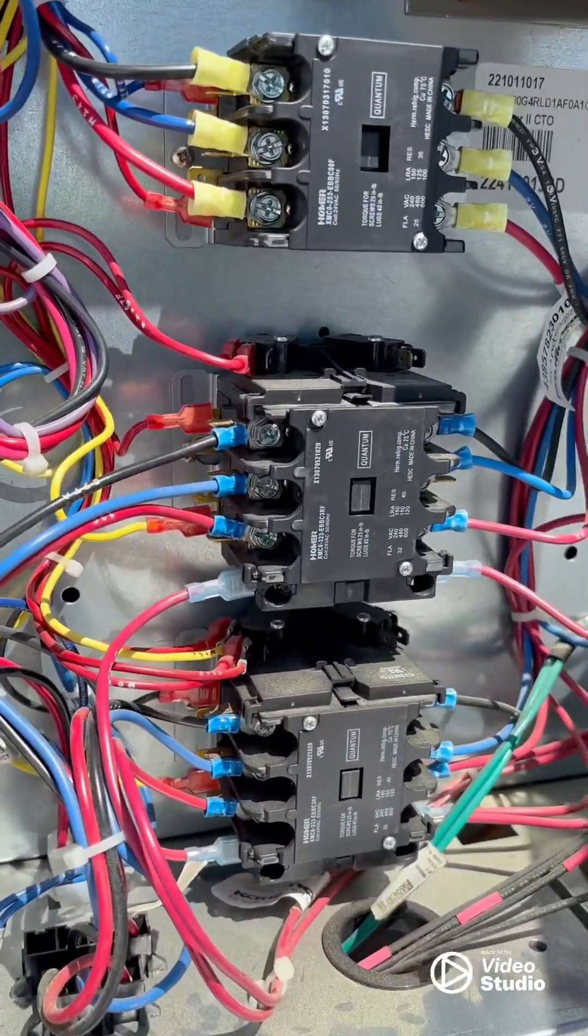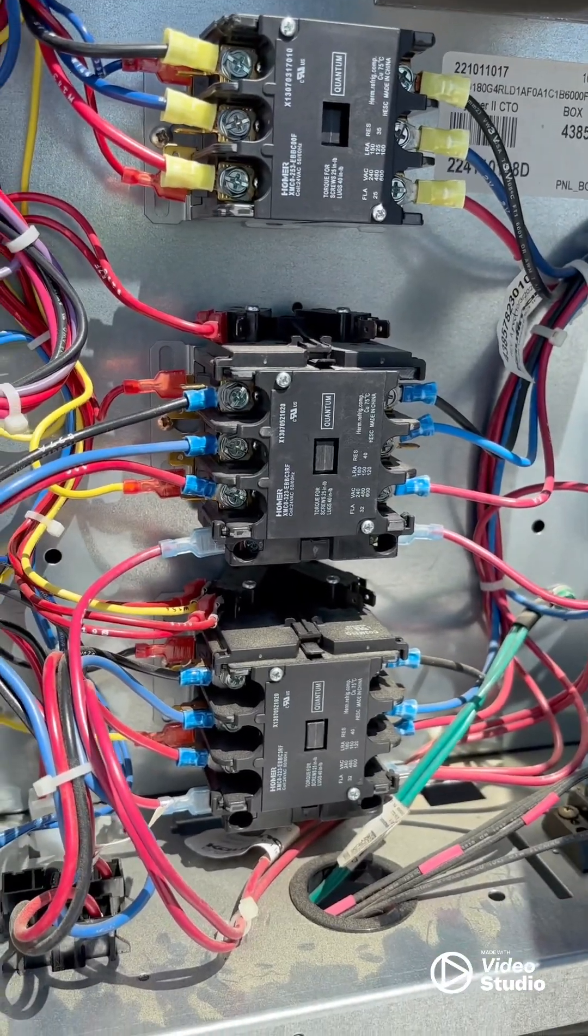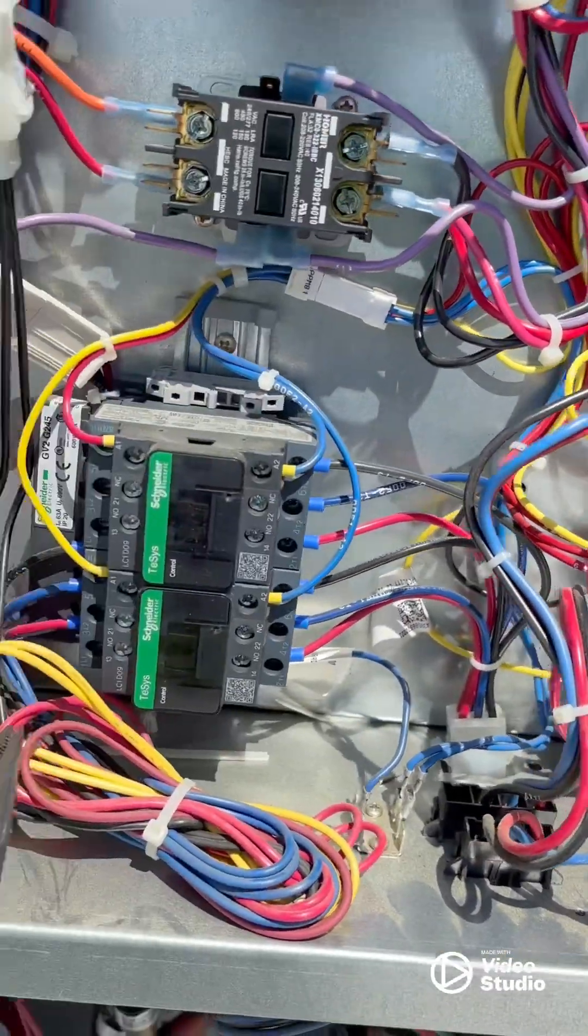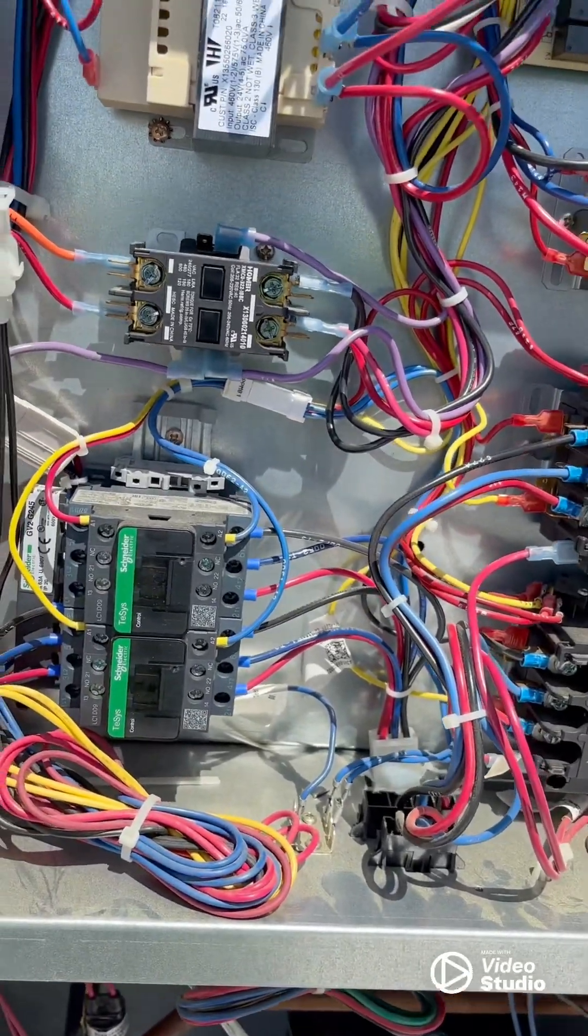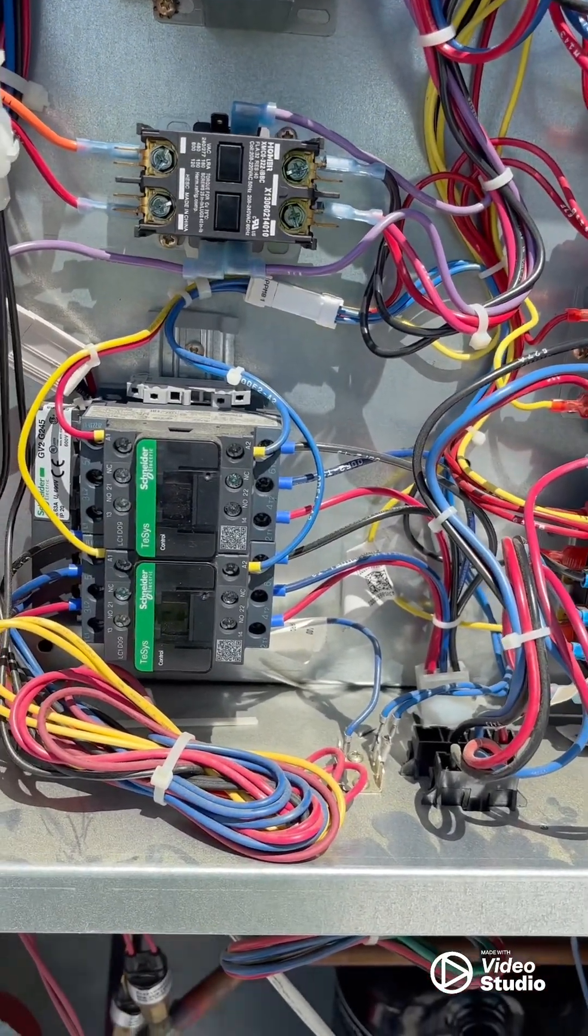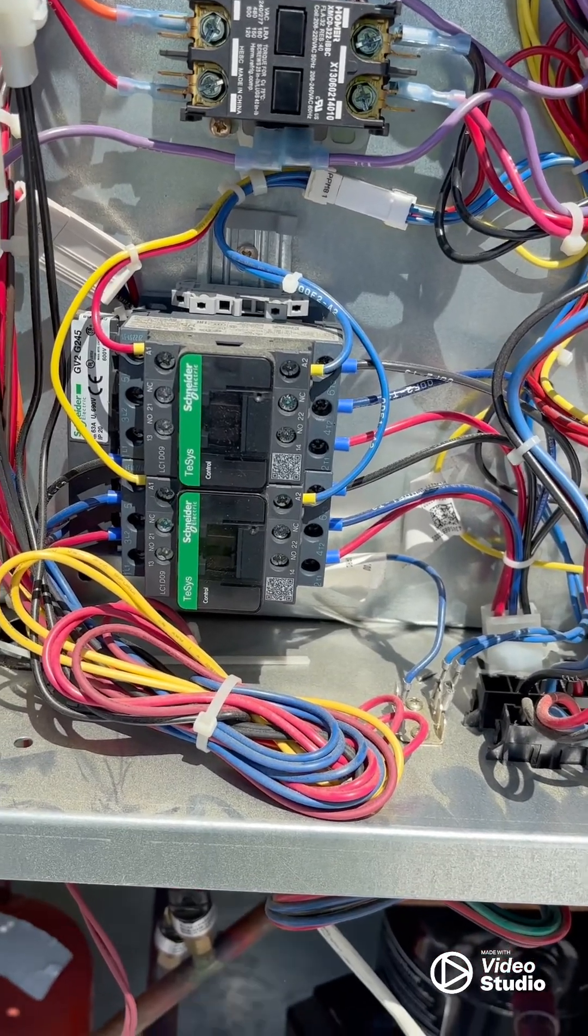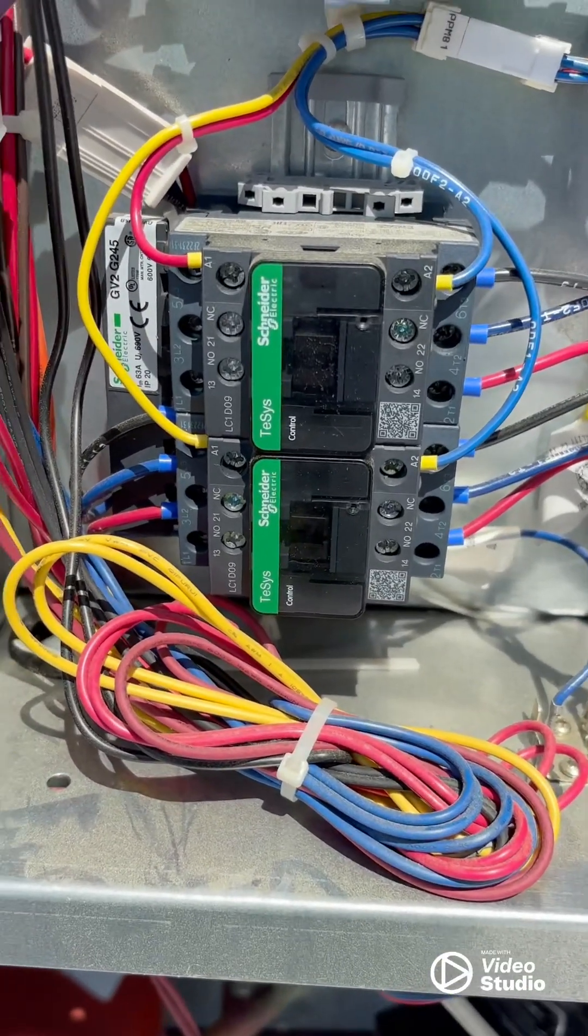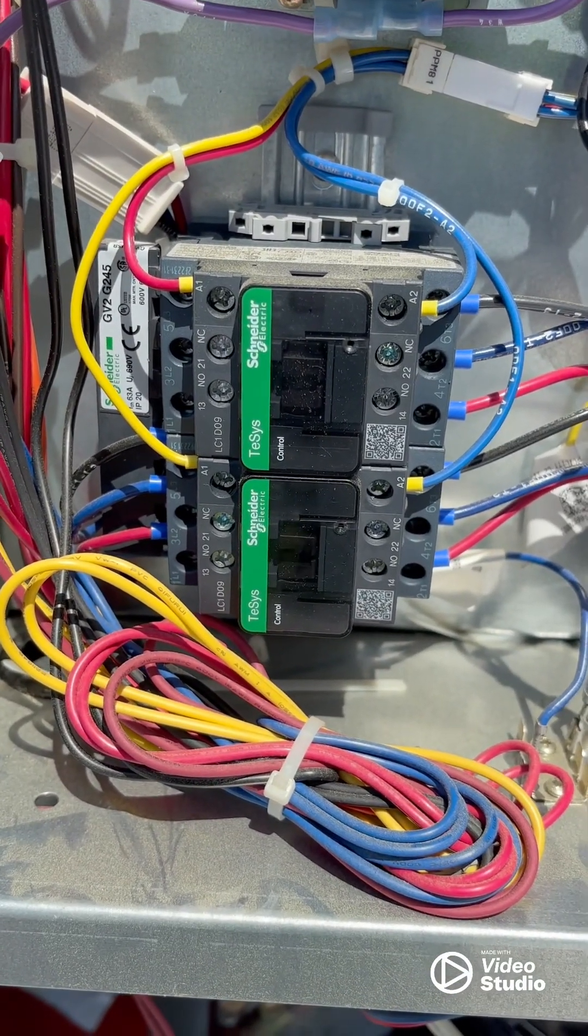That contactor is going to pull in, I think for a split second. No, it's not going to pull in. The fan contactor is going to pull in for like a split second and it's going to trip out because it's not seeing voltage coming out of this board. So watch the fan contactor, it's going to pull in for a split second then trip back out.